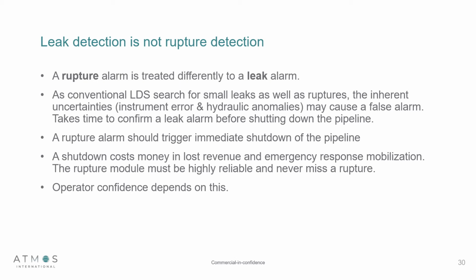This came about during the discussions raised in the API 1175, and the 1175 has a number of important principles that we should listen to. One, it talks about the continuous improvement and testing of leak detection systems that I've so far discussed with you, but more importantly, it discusses that we need to start treating a leak, a theft, and a rupture as three different characteristics, and make sure that our system can handle these three different scenarios. So as it stated, a rupture alarm is treated differently to a leak alarm.